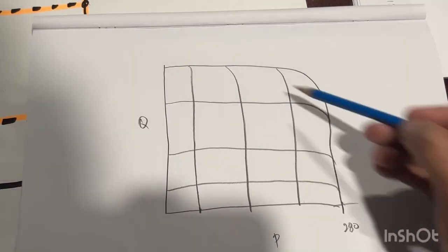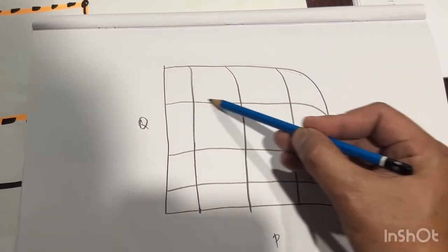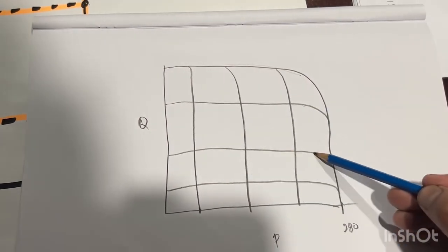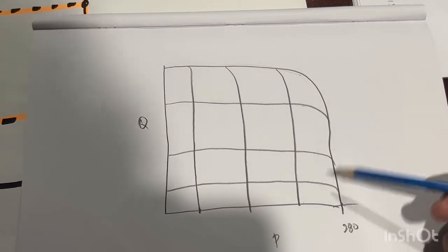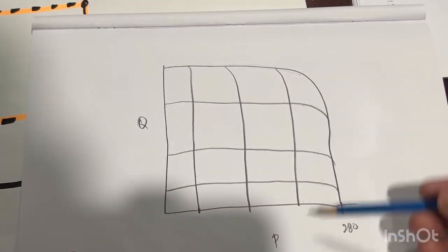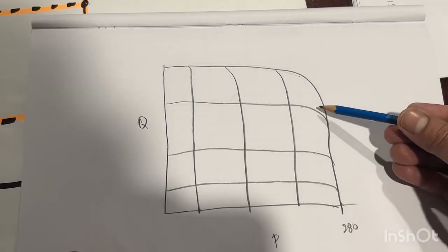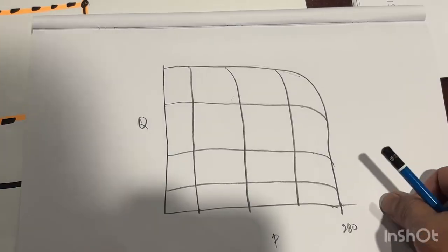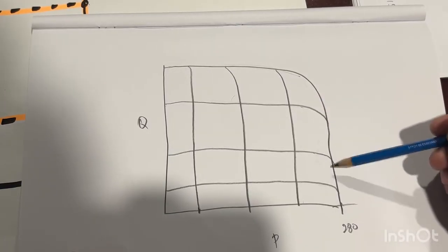This is the load sense. You can set the flow here through the control valve. You can set the flow here by regulating the control or throttle valve, and you can set the flow here regardless of pressure and RPM. Once the flow is set regardless of pressure, it will not change unless the pump efficiency is bad, then it will change because you have too much leakage, or unless the load almost reaches the pressure cutoff, and because it almost reached the pressure cutoff, the swivel is regulating to minimum.